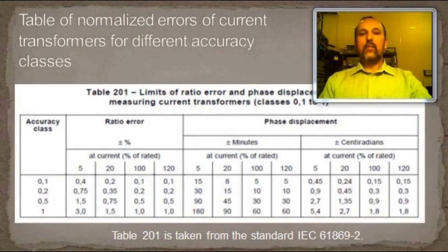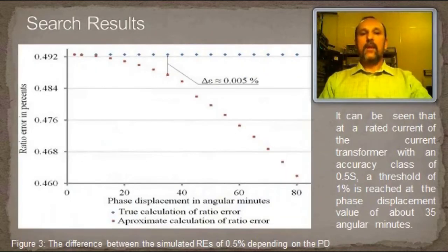Looking at table 201, it is seen that the allowable value of the phase displacement is 30 minutes. In figure 3, it can be seen that at a rated current of the current transformer with an accuracy class of 0.5s, a threshold of 1% is reached at the phase displacement value of about 35 angular minutes. It is worth noting as that for the current transformers that meet the requirements of the IEC standard for accuracy.